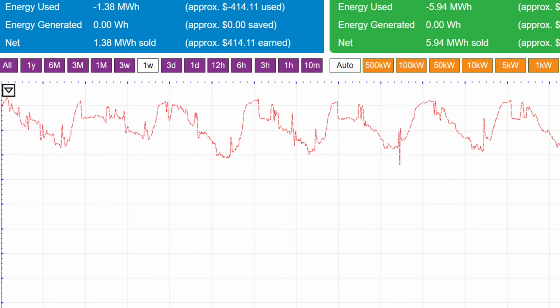The depth of that valley is like 3 or 4 in the morning. And then at the middle of the day are those peaks. And then the next valley is the following night. So look at each peak and valley, peak to valley, as a day. So what I'm showing you here is 1 week of easy cycling of this 30-ton Carrier chiller between a low of 7,000 watts at night to a high of 9,000 watts during the heat of the day.